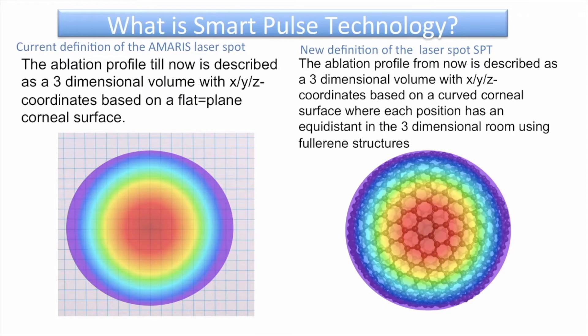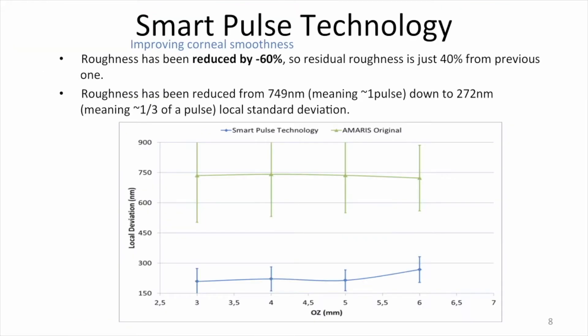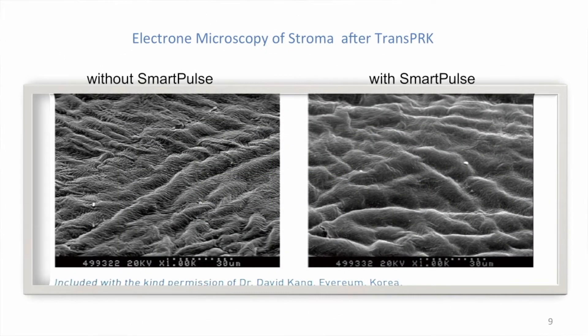The concept of TransPRK with SPT is what we call smart surface. We see the differences in roughness with and without Smart Pulse Technology. The reduction is about 60%, from 749 nanometers down to 272 nanometers. This roughness can be observed on electron microscopy from Dr. Kang, showing that the surface of the SPT TransPRK is smoother.